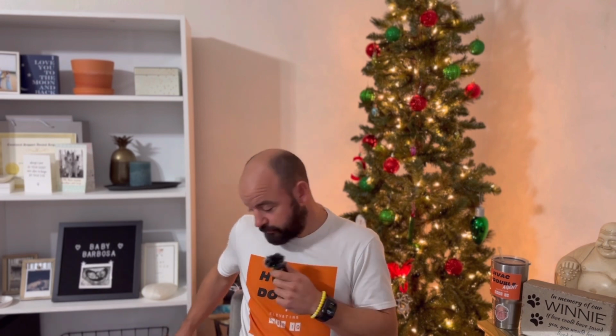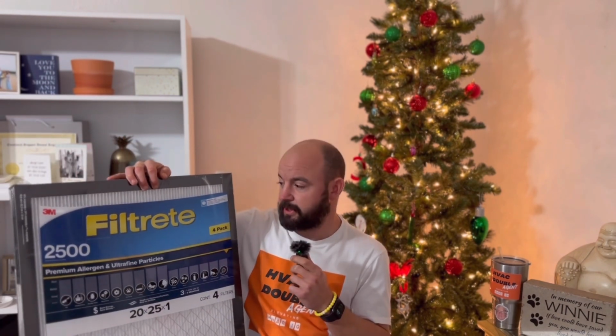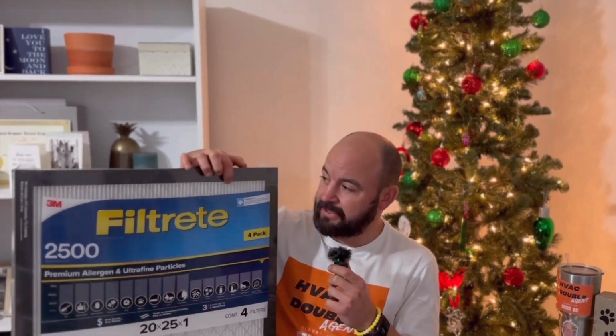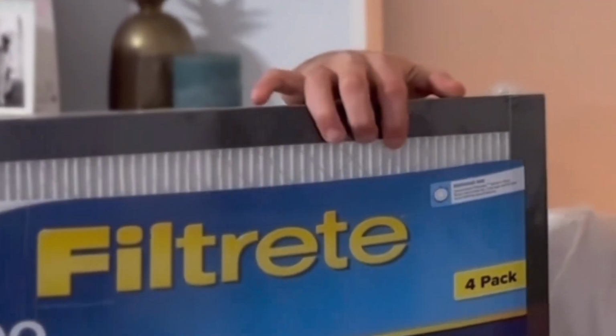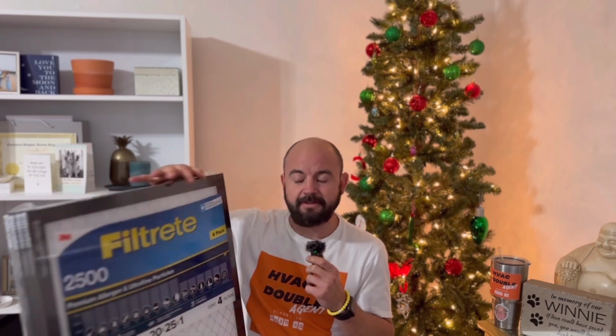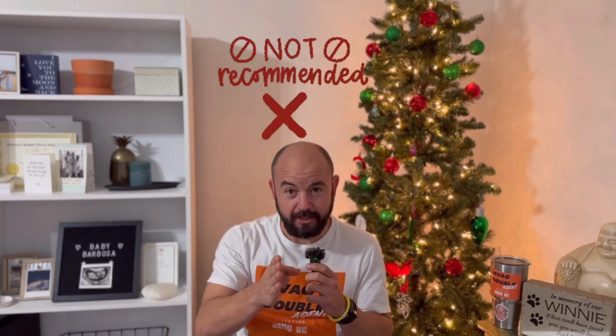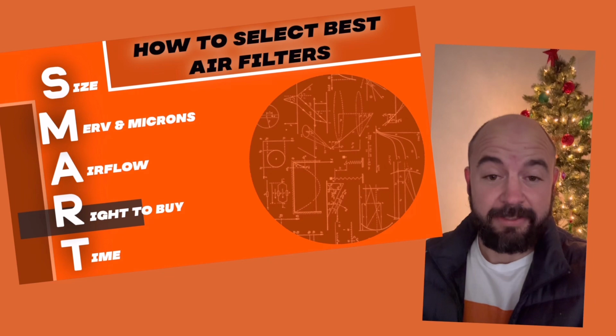It wasn't too long ago where I used to tell people if they use filters like this, Filtrete 3M, the ones with tons of pleats, as soon as I'd see these in a customer's furnace filter cabinet, I would immediately tell them these are terrible filters. They restrict your airflow and will kill your system prematurely, which they absolutely can if you don't know how to select the right air filter. But you're watching this video, and I'm going to show you.